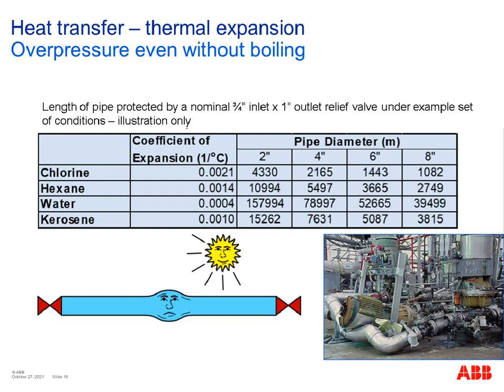So as you can see from those coefficients, the most onerous one is chlorine with the highest coefficient, and the lowest one is water. But in the case of solar gain, where you've got a pipeline being warmed from the sun, it's actually possible to protect a very large length of pipeline with a very small nominal relief valve. So a nominal thermal relief valve would be thinking about a 3/4 inch inlet to 1 inch outlet relief valve. Just a small standard thermal relief valve, and you can protect large lengths of line with a thermal relief valve like that.